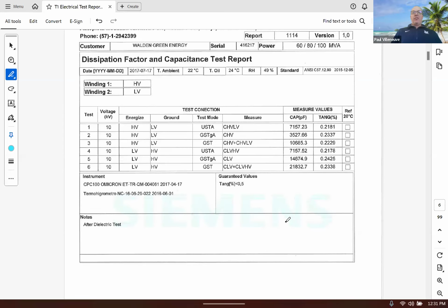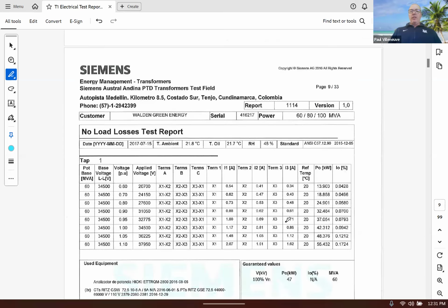So now we can start to go to the load loss or the no load test. We'll start off with the no load losses. And what we see is a bunch of data, as people were talking about when they were entering into class. The no load test is the open circuit test, which says apply rated voltage to one of the windings and measure the current. Rated voltage is 34.5 kV. So to gather your data, you should have been using that row right there, right? You don't want to run it at 20,700 volts, because is that rated voltage? Not even close. So you wanted it to be that value.